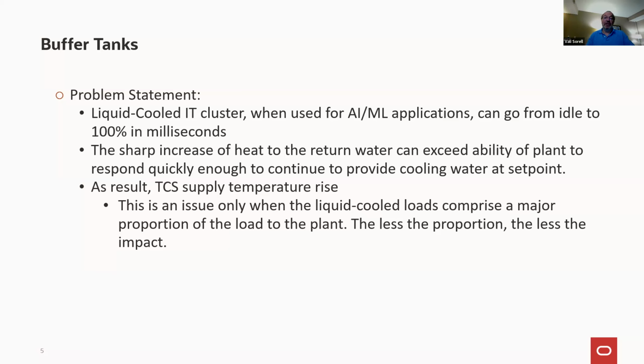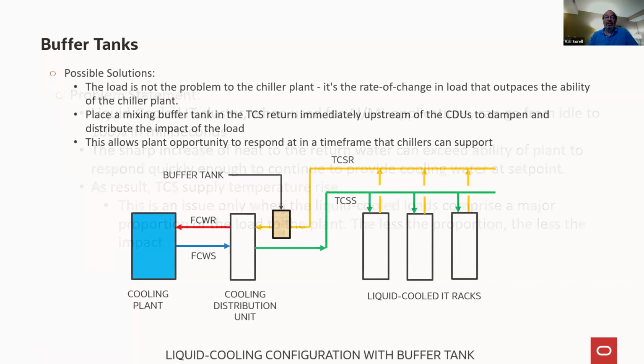It gets transferred to the chilled water, and it hits the chiller plant, which for most of the time has been operating very pleasantly at maybe a 30 C return temperature, and all of a sudden it gets hit with 40, 45, or 50 C water, and no chiller is going to operate through that. The moment it sees that, it'll shut itself down, and all of a sudden the whole system comes down, and there's not anything you can do about it. So the proposed solution is to put a buffer tank in the return of the TCS, so before it goes into the CDU.